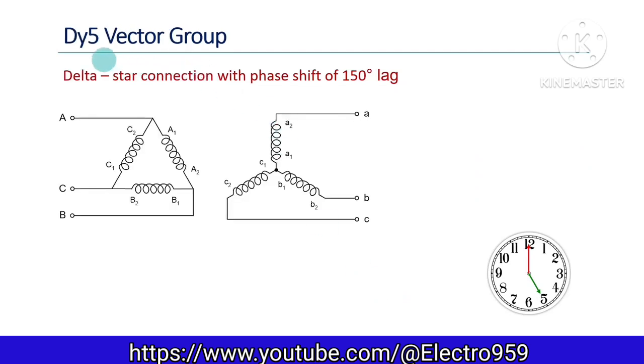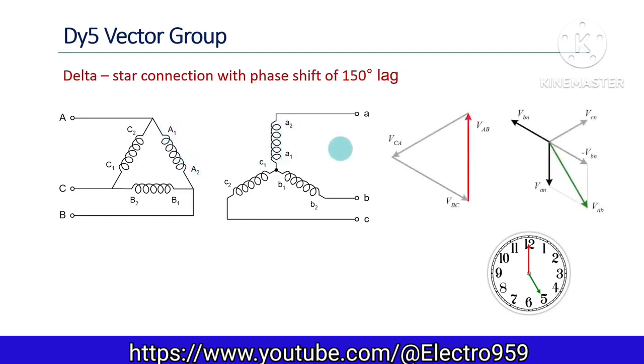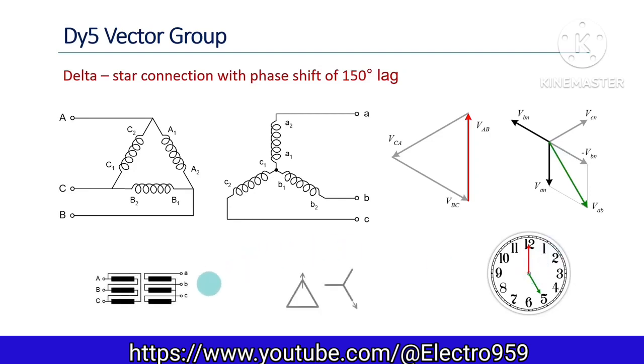In the DY5 vector group, the primary is delta connected and the secondary is star connected. Note that the polarity of the secondary side windings is changed here — the positions of A1 and A2 are interchanged. Therefore, in the phasor diagram, the voltage induced in winding A of the secondary will be 180 degrees displaced from the primary side line voltage. Similarly, the VB phasor is also displaced by 180 degrees. The line voltage VAB in the secondary is obtained by VA minus VB, resulting in the secondary line voltage lagging by 150 degrees — the 5 o'clock position holds good in this case also. The simplified connection diagram and displacement diagram are shown.